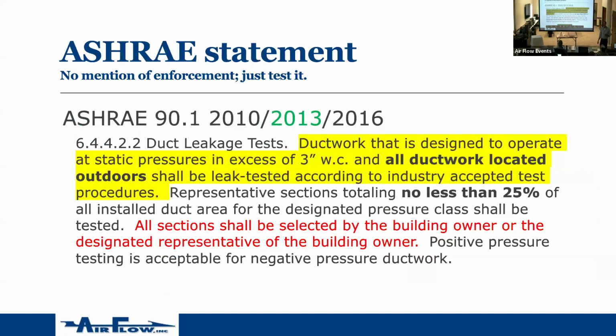I think we're 2013, right, everybody? Now, we have no ductwork here that's tested at 3 inches. That's like class B, like medium pressure. Almost everything in, Ben was in the sheet metal trade not too long ago, it's either high or it's low, right? So all ductwork outdoors is supposed to be tested. How much of that is tested? I've never gotten a pressure test report, ever, even with Thermaduct.